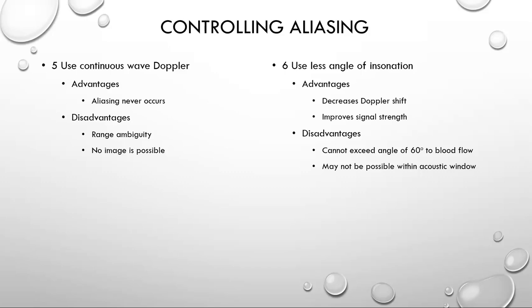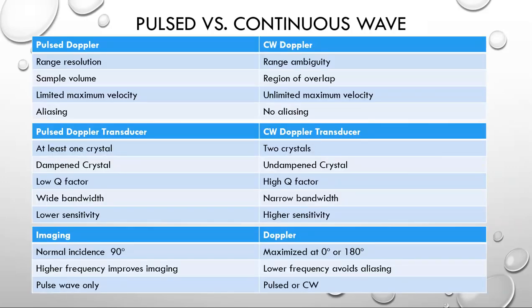Summarizing pulsed versus continuous wave ultrasound: pulsed ultrasound gives range resolution, has a sample volume, limited maximum velocity, and aliasing. It requires only one transducer, has a low Q factor, wide bandwidth, but lower sensitivity. Continuous wave always has range ambiguity, never has aliasing, requires two crystals, is undampened so it has a high Q factor and very high sensitivity.